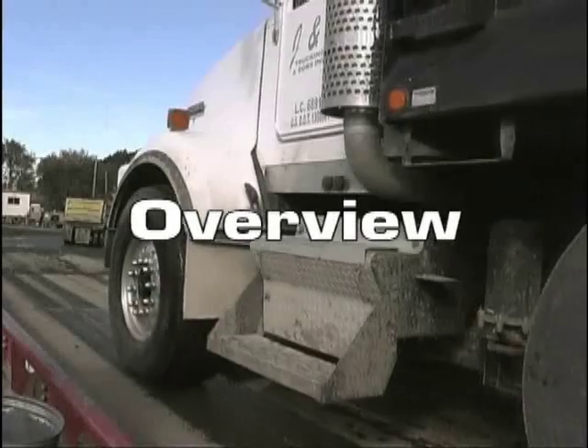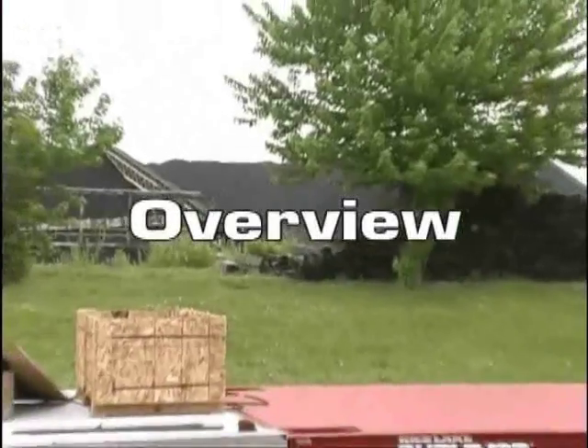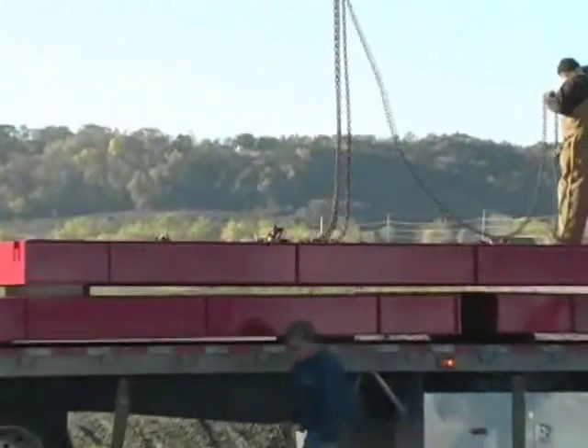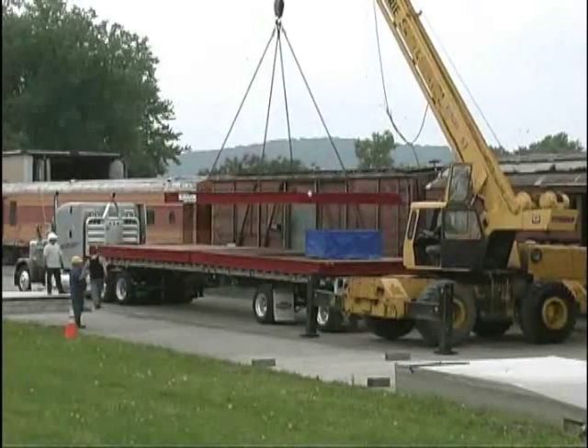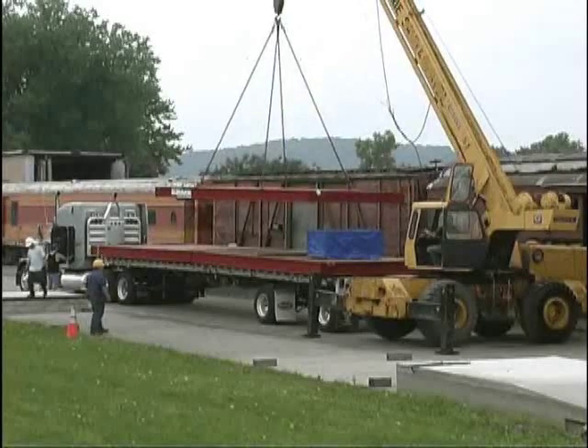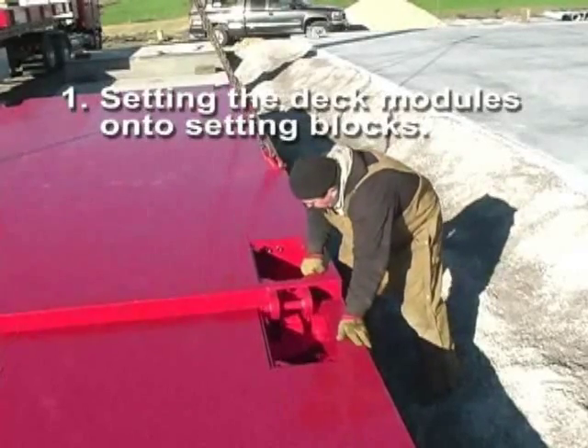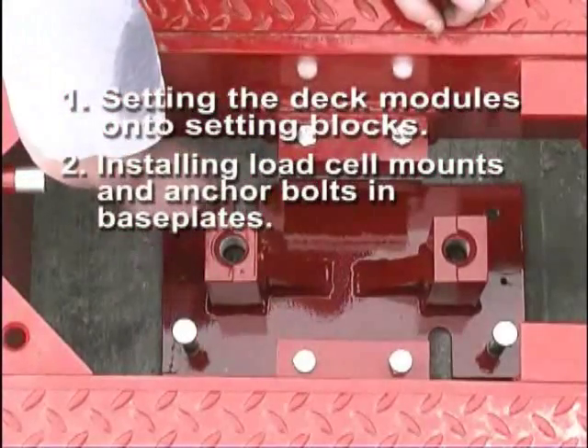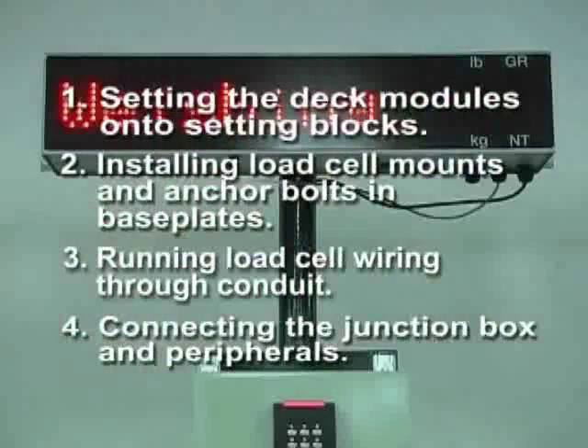This video provides an overview of installing a Rice Lake Weighing Systems Survivor OTR Series Steel Deck Truck Scale. The modular sections of the OTR Series Truck Scale are shipped pre-assembled and ready to be placed into position on temporary setting blocks using a crane. The general assembly order covered includes setting the deck modules into position, installing load cell mounts in pockets and anchor bolts in base plates, running load cell wiring through conduit, and connecting the junction box and peripherals.